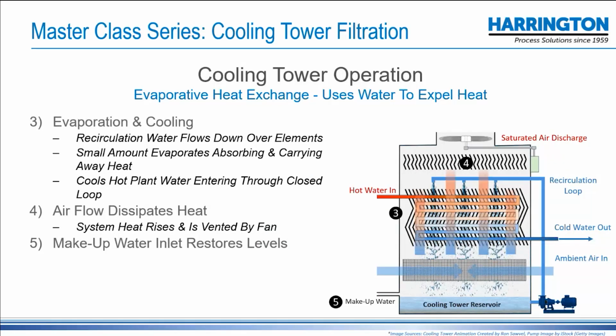And this is more of that description, and that the evaporation and cooling is again causing a heat exchange effect. The hot air is rising, cool water is dropping. There's a makeup water connection. And what's not shown here is there's always a drain so that they can purge the dirty water. And of course, as you can imagine, that can be quite a high level of water that has to be purged to drain the sludge out of that basin. And again, that's called blowdown, and that's referring to the sediment that is blown down into the reservoir.